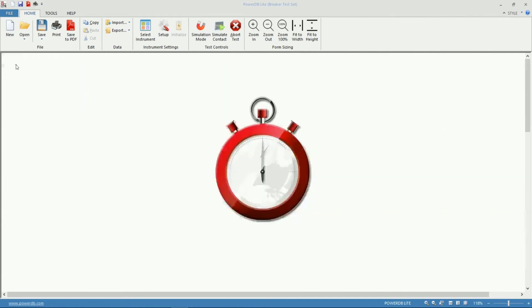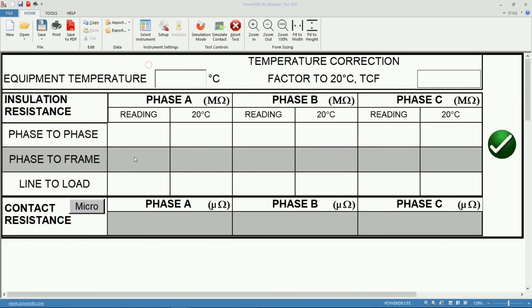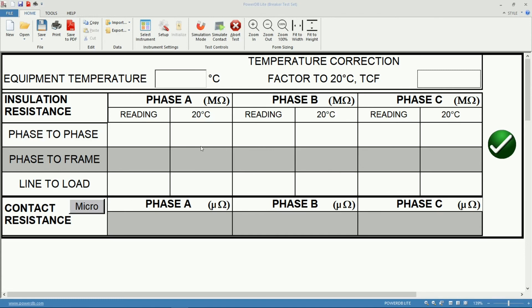I want to show you one more section of the software which is the resistances table. I have access to that table clicking on this resistor icon on the toolbar. Since whenever you do these measurements on a circuit breaker, most probably you will also be measuring insulation resistance and contact resistance. If you're doing so with one of our instruments, the S1 for example for insulation resistance and one of our DLROs for contact resistance, you can input those results in this table manually.